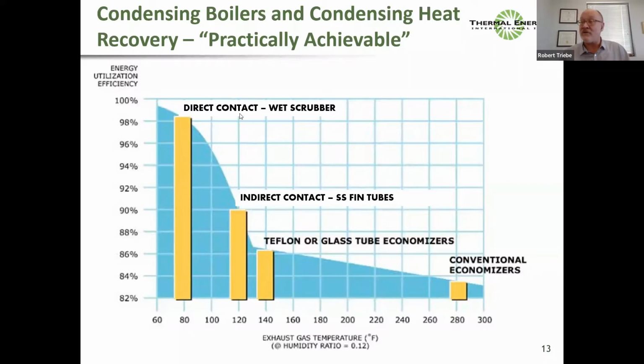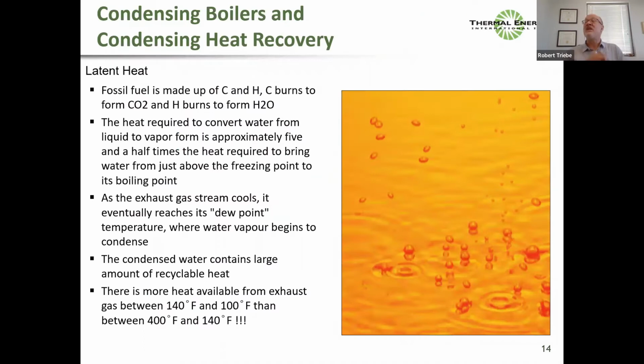It's most important to get the high efficiency that we're linking into cold users. Otherwise, we can't cool the flue gas down. So again, this is a graph of exhaust temperature versus thermal efficiency and the types of performances you can get from these different technologies. So a little bit more on that, because the bottom statement on this slide is one of my favorite statements. It might be one you're aware of, but it's not one that's commonly known. So I've explained the dew point and the vapor, but the bottom statement's the one I love the most.